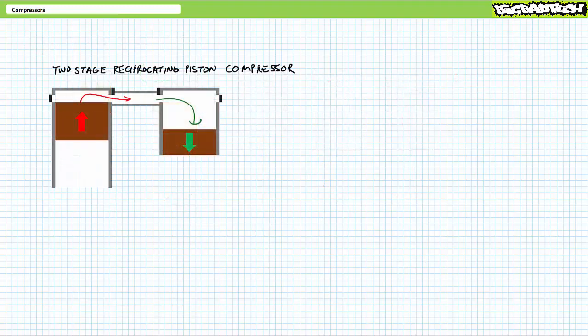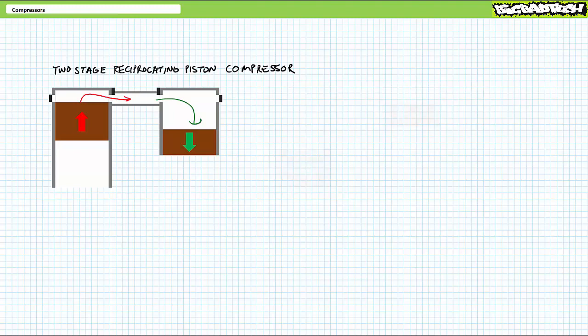Consider a two-stage reciprocating piston style compressor driven by the same shaft. While the primary cylinder is in the compression stage with an open outlet, the secondary cylinder is in the suction phase with an open inlet. Previously compressed air from the primary cylinder is drawn into the secondary. The other half of the cycle, the cylinders switch roles and the valves change states. The inlet in the primary opens and the outlet closes as the primary piston descends. The inlet in the secondary closes and the outlet opens as the secondary piston rises. The primary cylinder is in the suction phase pulling in more air from the environment, while the secondary cylinder is in the compression phase expelling the doubly compressed air into the pneumatic system. The process then repeats itself over and over. In this fashion, the primary cylinder sucks up environmental air, performs initial compression, hands it off to the secondary cylinder, which again sucks it up, further compresses it, and expels it into the pneumatic system.